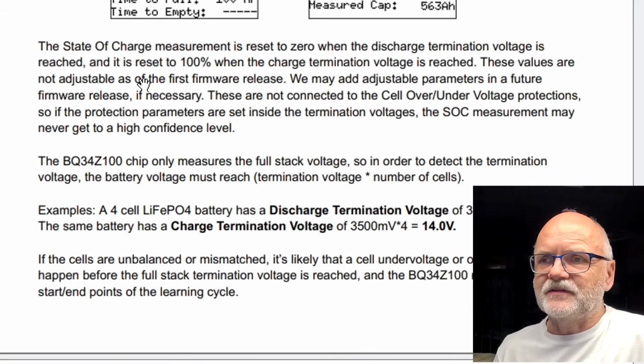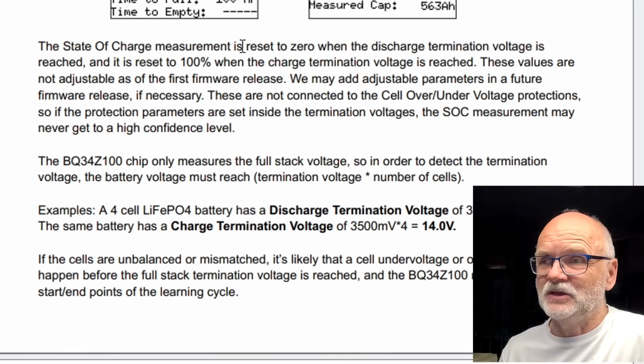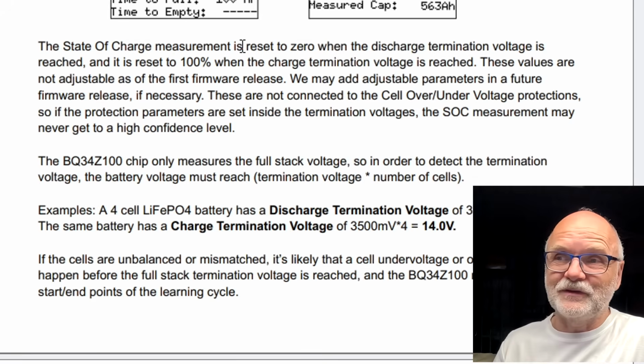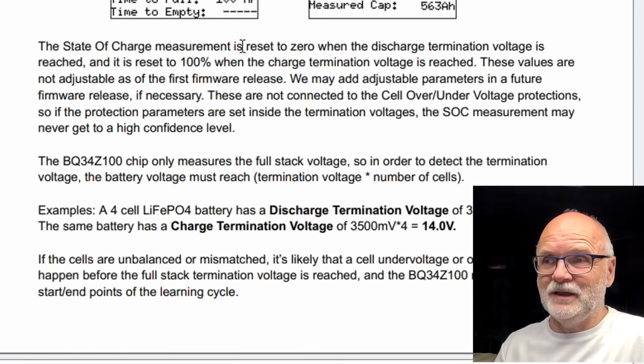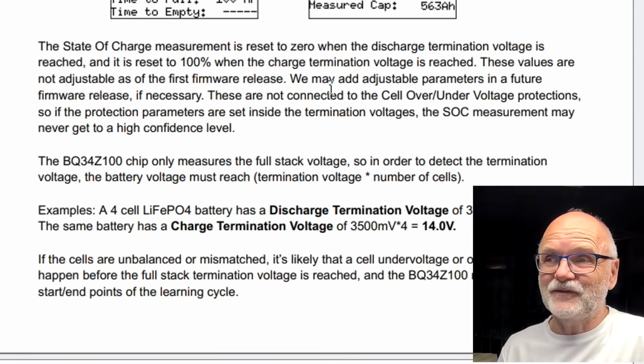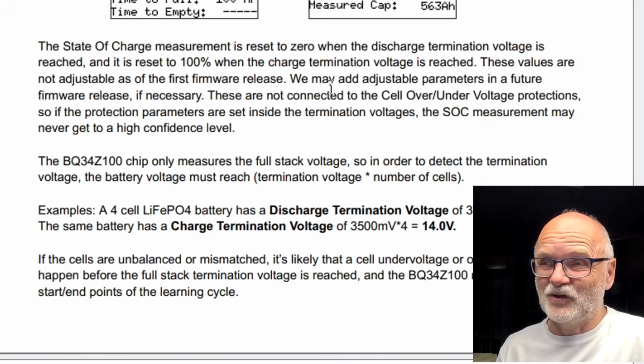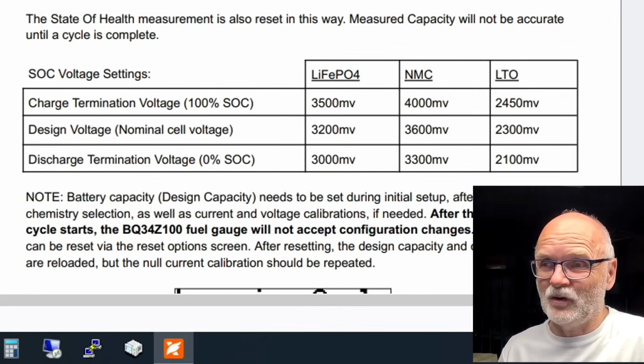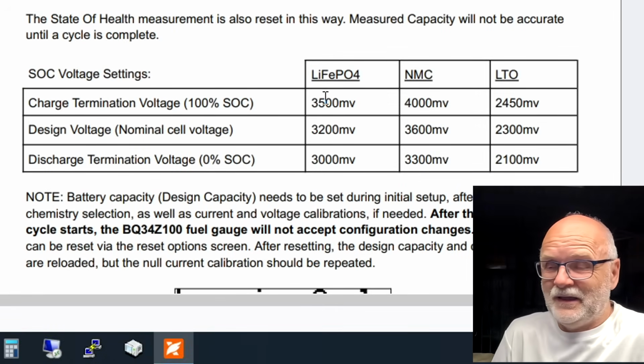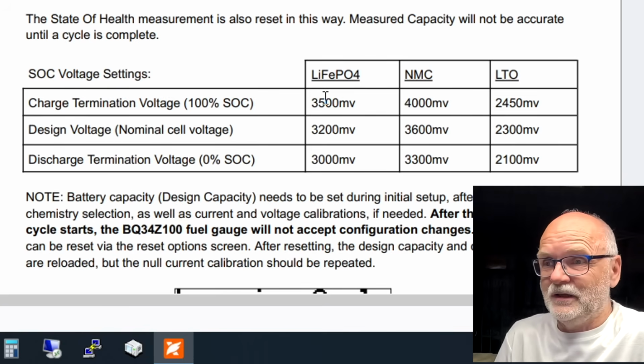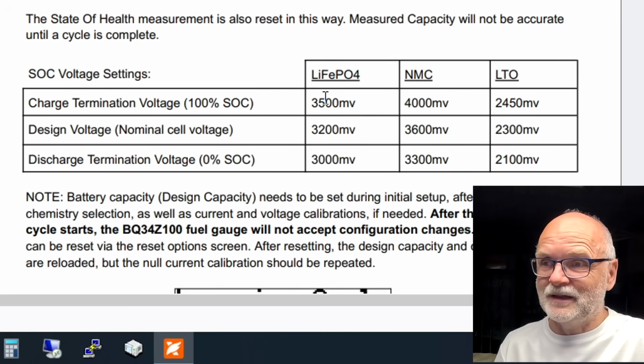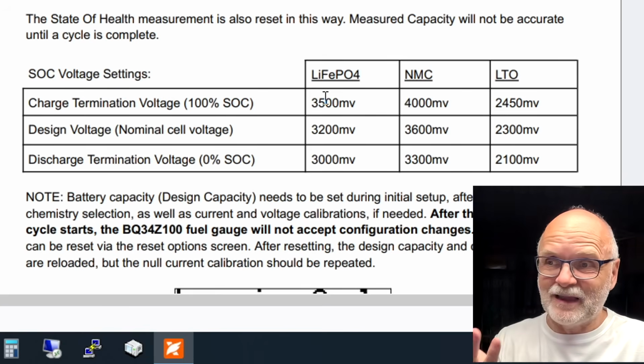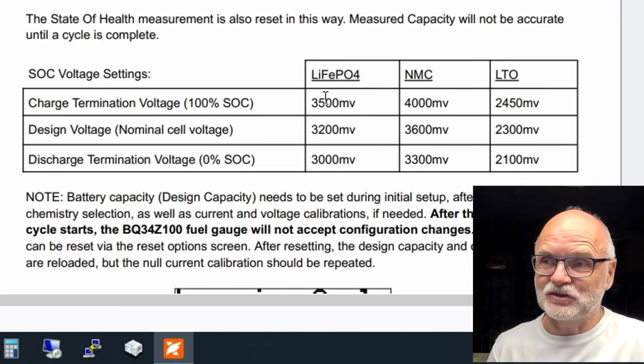So here it says the state of charge measurement is reset to 0 when the discharge termination voltage is reached, and is reset to 100% when the charge termination voltage is reached. Yeah, these values are not adjustable as of the first firmware release. So obviously it handles it only between 3 volts 0 and 3.5 100. Well, I never charged to 3.5 volts, so this BMS would never reset to 100%. But we will see, maybe we have an upgraded firmware already here and we can adjust these parameters.